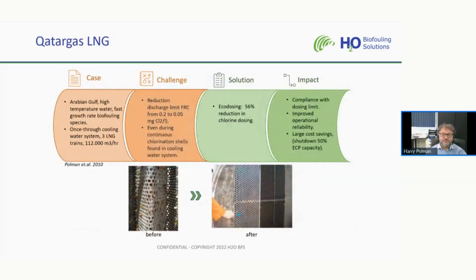An LNG plant in Qatar: over here also continuous dosing, still fouling in the system, and Qatargas was challenged to reduce the discharge limit from 0.2 to 0.05. We installed Ecodosing, we reduced the amount of chlorine dosed to the intake by 56%, and what we saw on this plant, in the picture on the right, is improved fouling control. No fouling in the system anymore, a clean system in comparison with continuous dosing. So with less chlorine, a cleaner system.